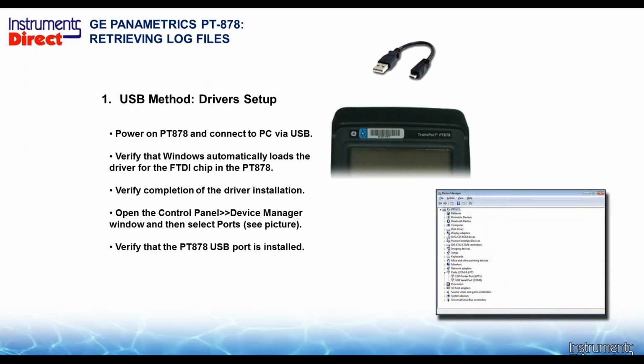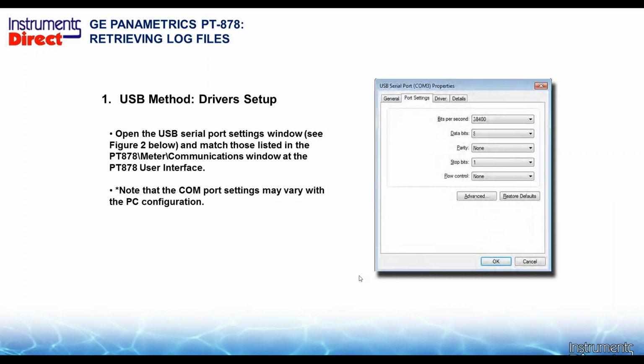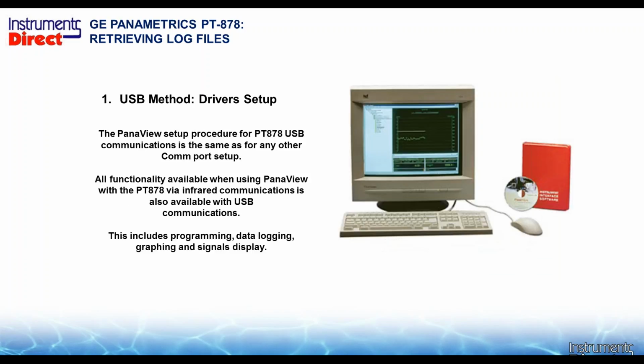So we power up the PT878 and connect it to the PC using the USB. We verify that Windows automatically loads the driver. We verify completion of the driver installation, and then we open the Control Panel, the Device Manager window, and select the ports. There's a picture here to the right on your computer. So make sure that the PT878 USB port is installed. So again, using the USB method, we need to set up the drivers. Open the USB setting port windows and match those listed in the PT878 communications window at the PT878 user interface. And note in this case, the COM port settings may vary with the PC configurations.